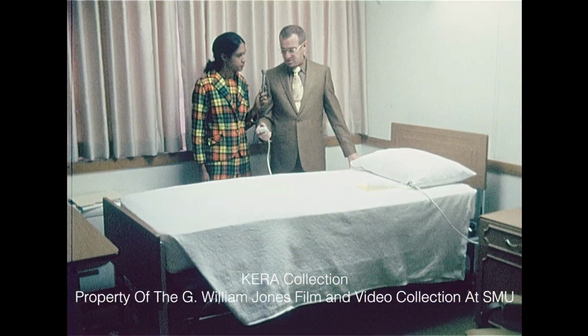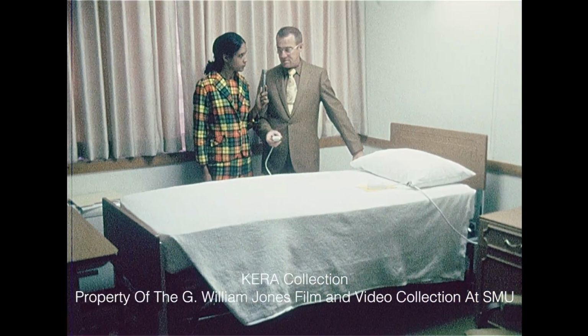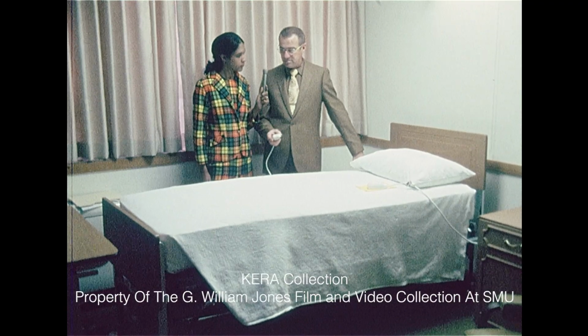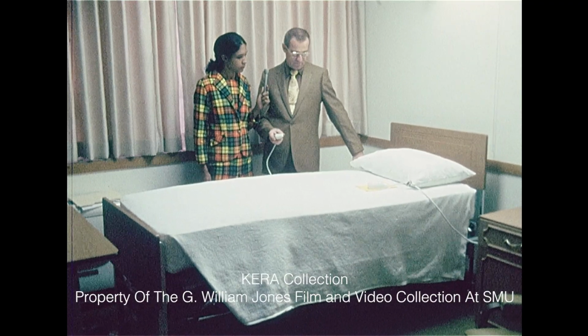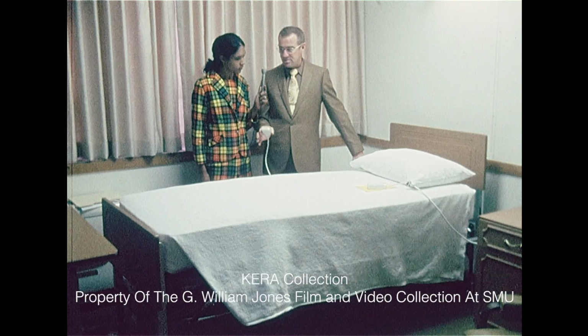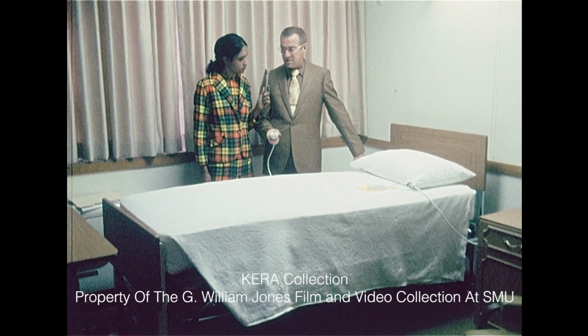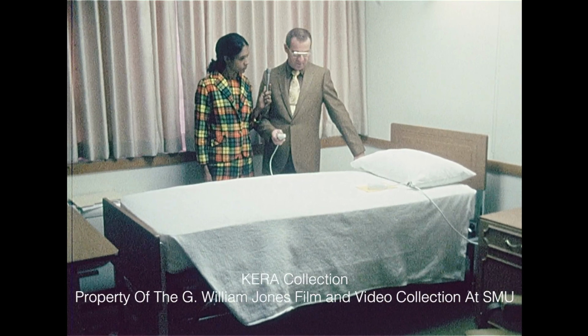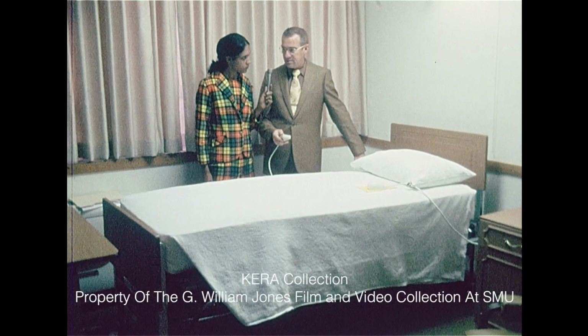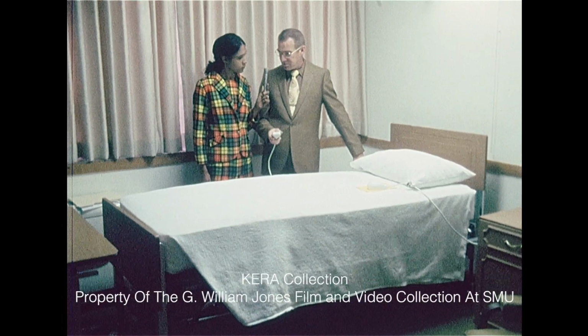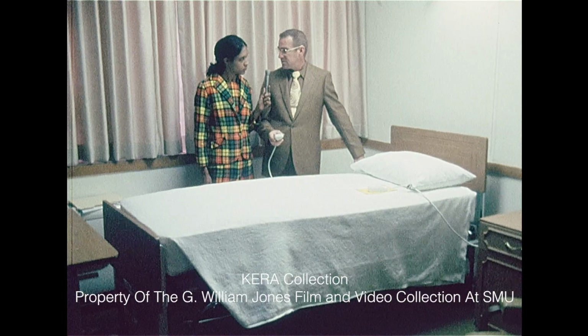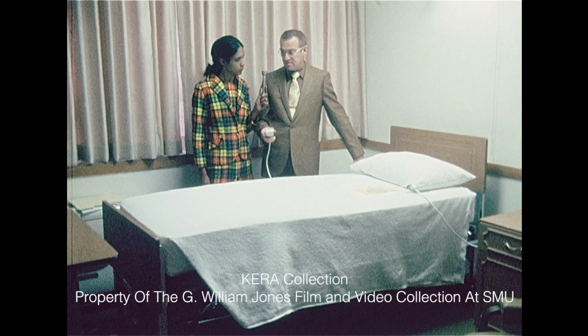This bed has two little 110-volt motors that are grounded. We have a circuit that we assure ourselves is on a preventive maintenance schedule and is checked once every 90 days for continuity to ground, to make sure that the bed is properly grounded and that there's no frayed wires or anything within the area.